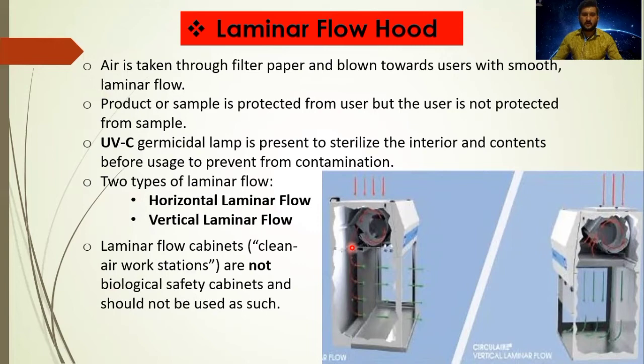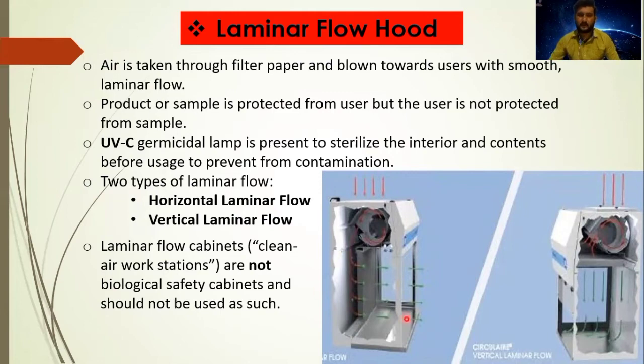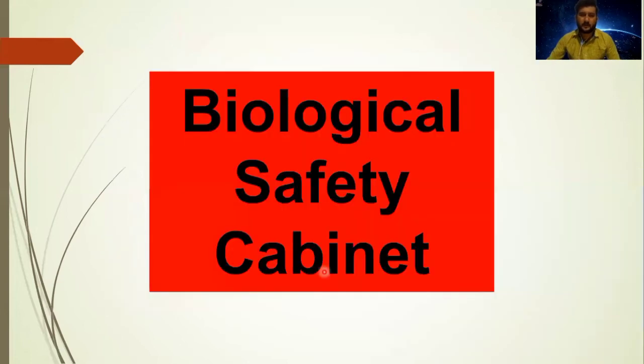Keep in mind that according to WHO, laminar flow cabinets are not used in place of biological safety cabinets. The laminar flow hood cannot be used as a substitute for the biological safety cabinet.